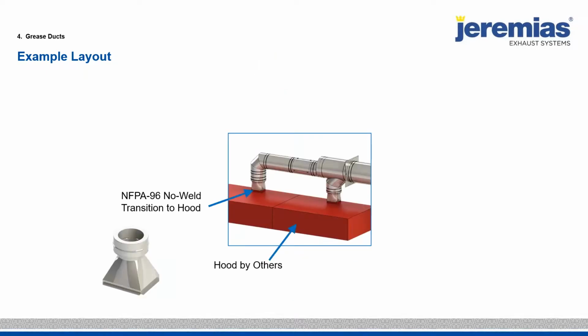So the hoods are by others, so you want to make sure you are specifying a no weld transition or hood adapter. A lot of hood manufacturers are making round collars today. Most of them ship it out with the collar not attached when they're going with another ductwork system. So we have a no weld hood transition that connects to a hood that has no collar on it as an option as well.